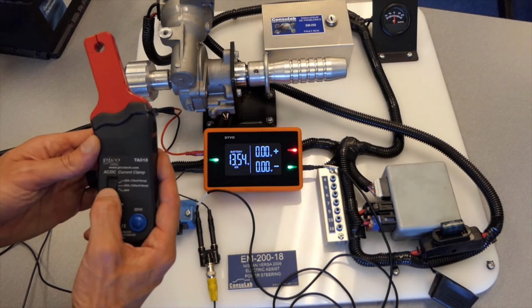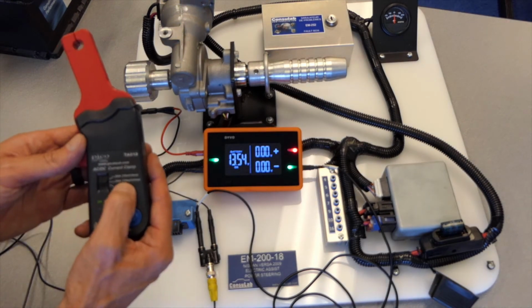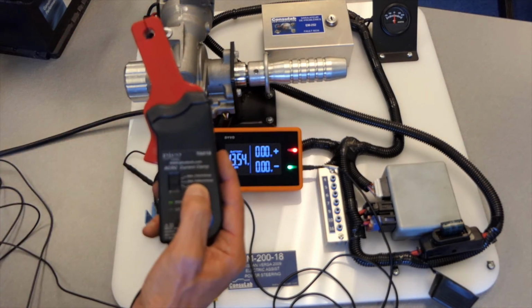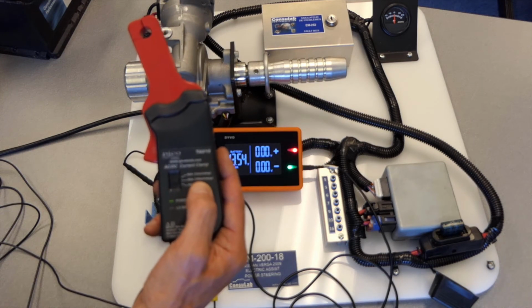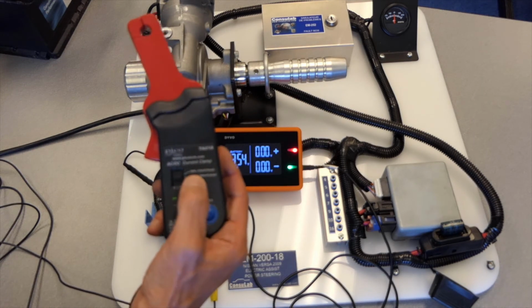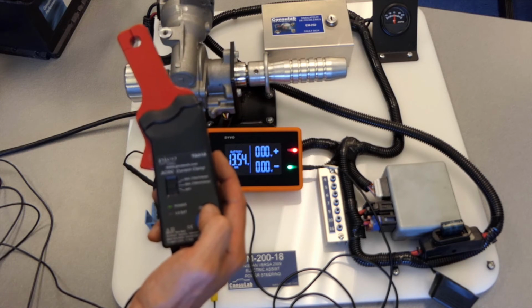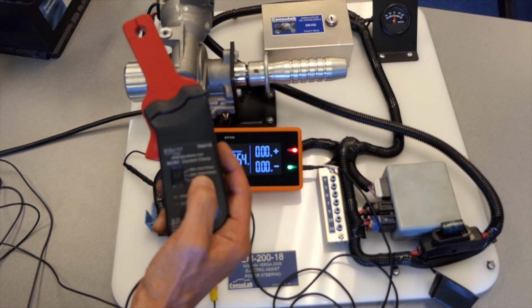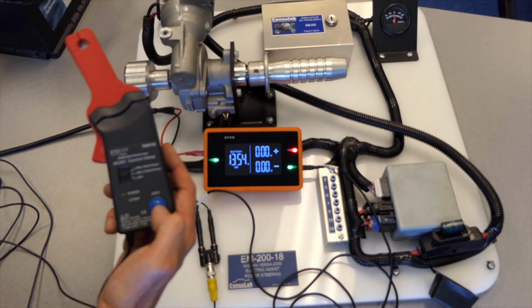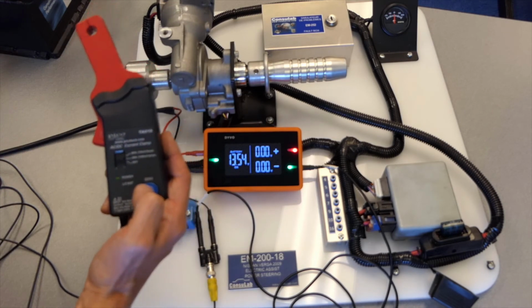I'm going to turn the amp clamp on. Notice here that our scaling in the 20 amp mode is 100 millivolts equals an amp. We may have to bump this up to the 60 amp scale, I'm not sure yet, but we need to keep in mind that every 100 millivolts equals 1 amp. I'm going to zero the clamp out.